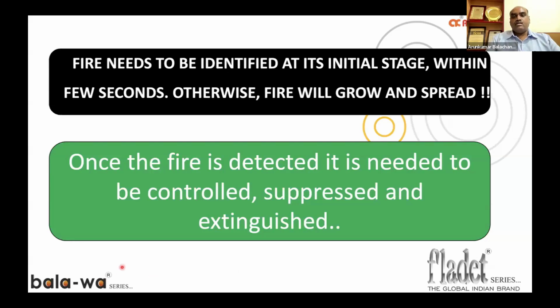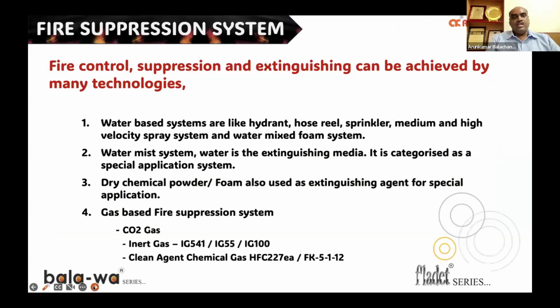So what we are going to do is first bring the fire into a controllable stage. Then we are going to suppress, that is bring down the temperature to less than 100 degrees centigrade, and then finally extinguish the fire. To fight the fire, we have many technologies, and the available technologies are water-based systems like hydrant, hose reel, sprinkler, medium and high velocity spray systems, and water mixed foam system. Water mist system, which is essentially water as the extinguishing media, is categorized as a very special application system. A dry chemical powder and a foam system are also used as extinguishing agents for very special applications like oil fires. And finally, we have the gas-based suppression systems like carbon dioxide, inert gases, and chemical agents like HFC 227 and FK 5112.